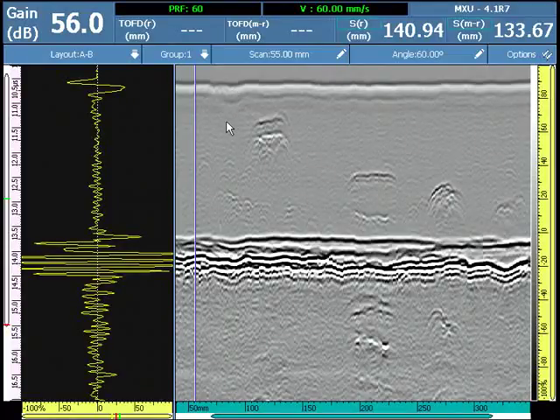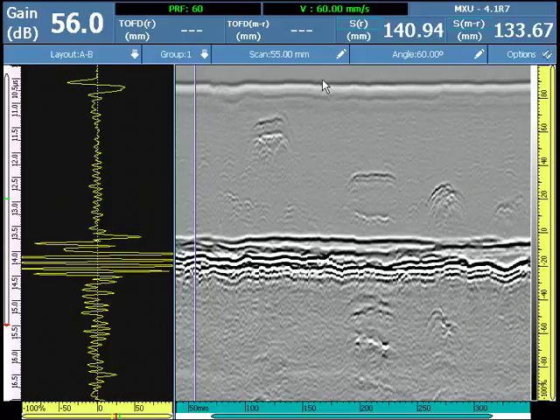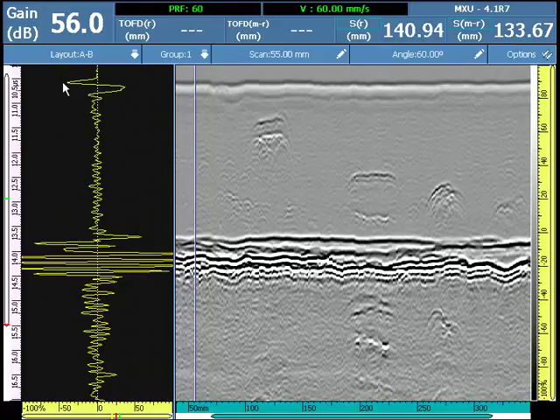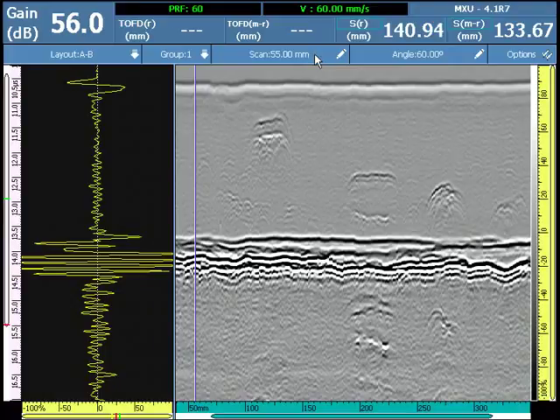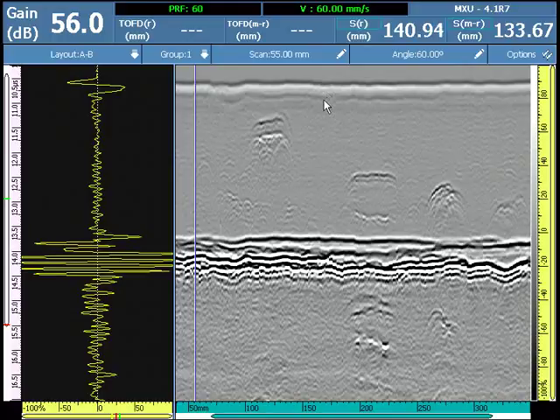The OmniScan Lateral Wave Straightening Tool is designed to straighten the lateral wave by aligning all of the A-scan's lateral wave first peak signal with one reference A-scan selected by the operator, here at 55 millimeters.